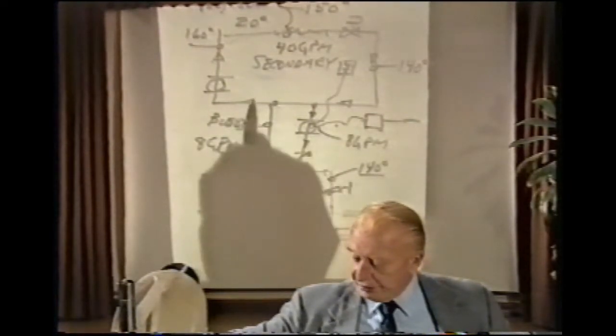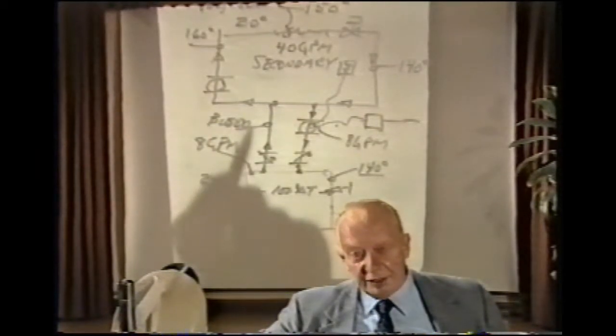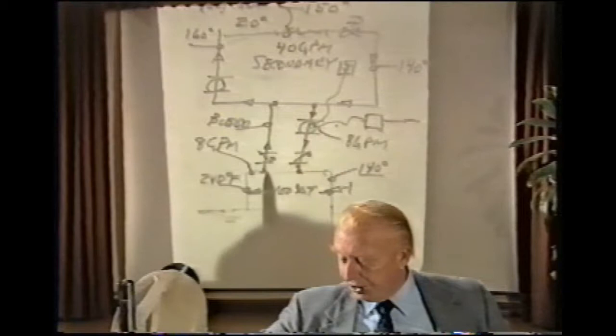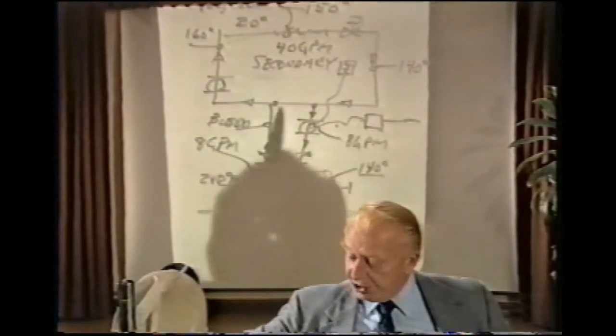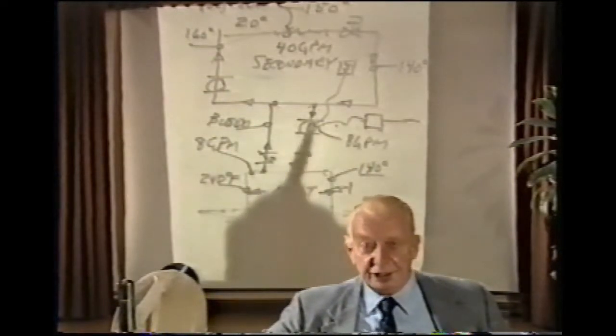So the necessary thought provision here then is what will happen to flow in the common piping. In this illustration, we have common piping also in the secondary circuit. In order to understand how flow in the common piping affects mix and operation of a system using primary-secondary pumping, we shall have to establish an ancient law which basically states that flow into a T must equal the flow that leaves the T. In this circumstance, we'll consider the T connecting the bleed line into the secondary circuit.